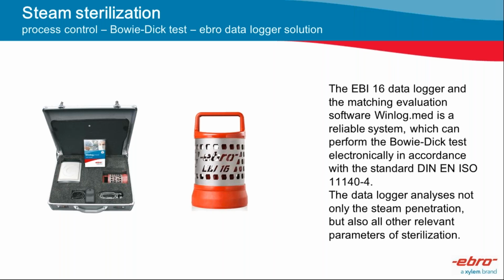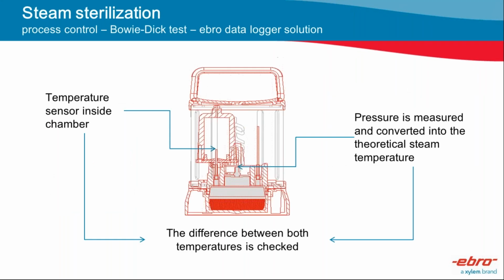Normally, if you hear about Bowie and Dick tests, you are talking about chemical indicators all the time, but not anymore with this kind of technology. And just to explain to you how it looks like, the Bowie and Dick test logger is actually a PCD, or what we call a process challenge device. It simulates the kind of testing that you perform using chemical indicators. And I apologize to Kolthoff, but maybe in the near future, we say goodbye to chemical indicators.